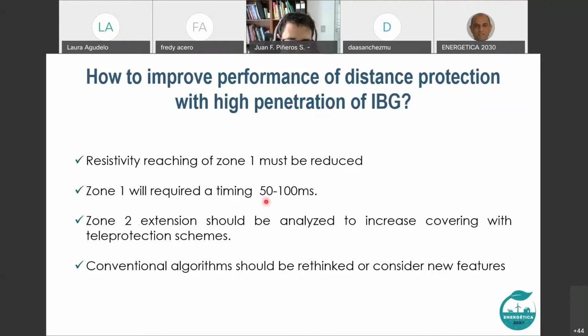Normally, you know, we don't put a timer in this zone, but according to the behaviors we are observing of the impedance that is almost vertical, we have to. Zone 2 should be analyzed too, to increase the coverage and to work better in combination with teleprotection schemes. Why? Because if we reduce zone 1 so much, we can compensate if you have teleprotection schemes, working with a scheme like POTT, so we have to study increasing it. Of course, if you increase zone 2, you have the challenge of checking how much you can increase it without having the overreaching problems we are describing.